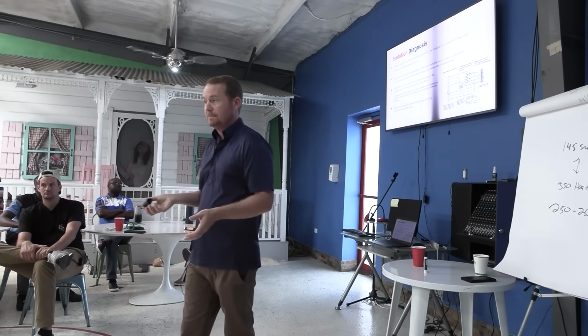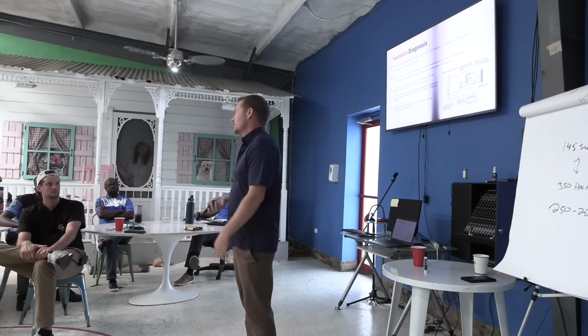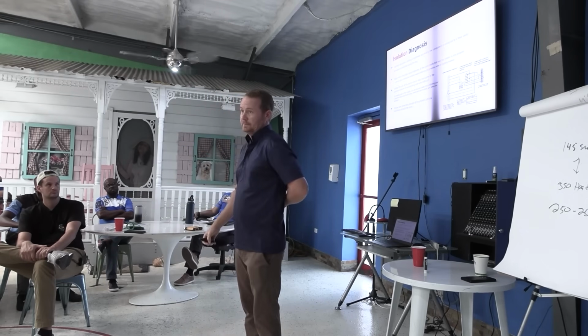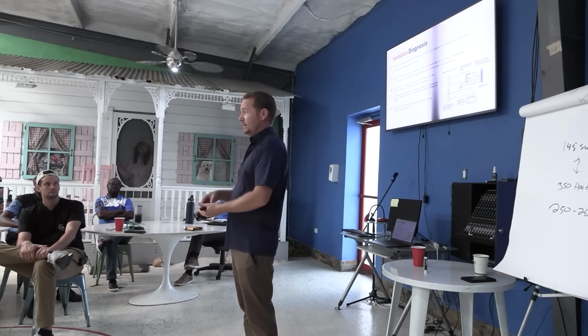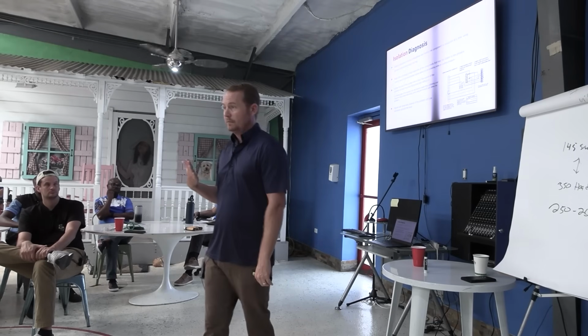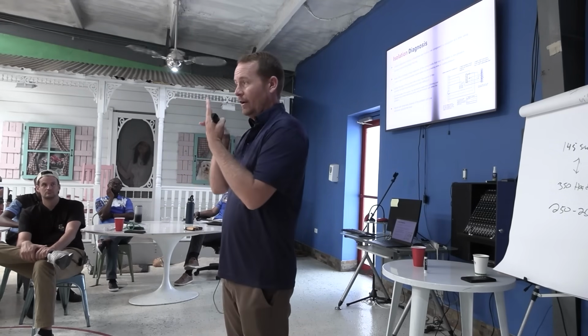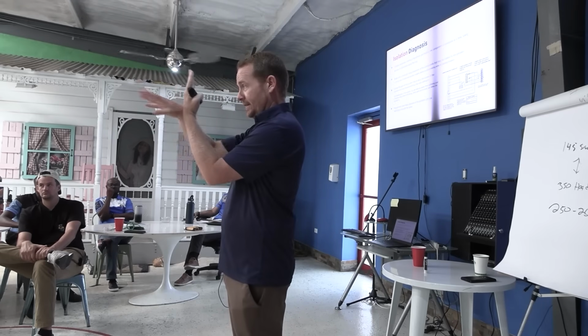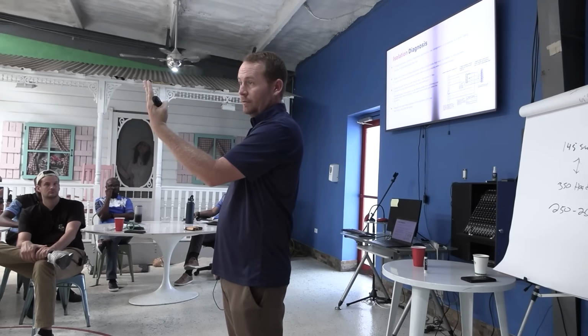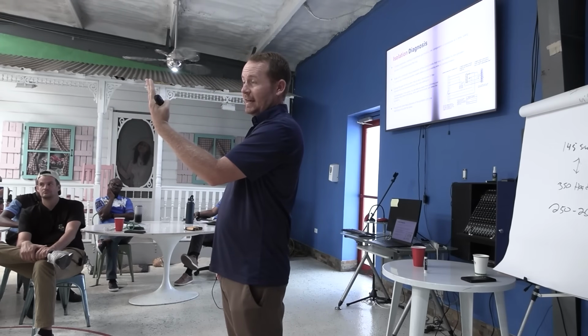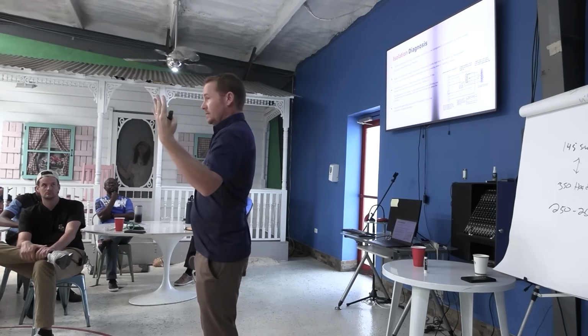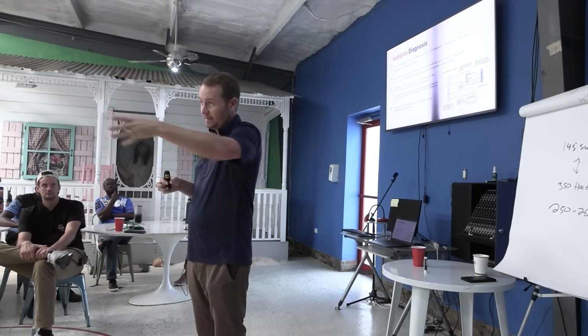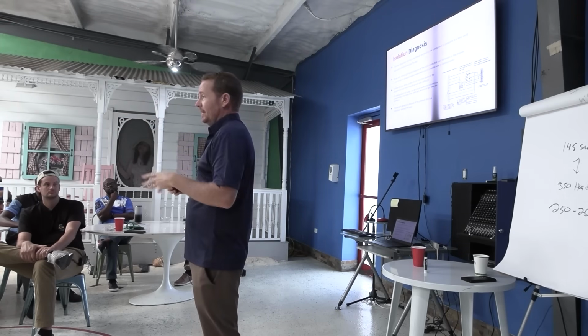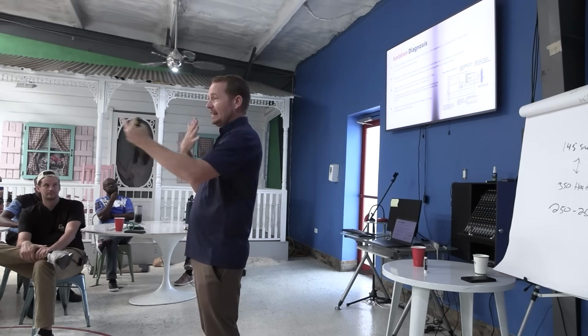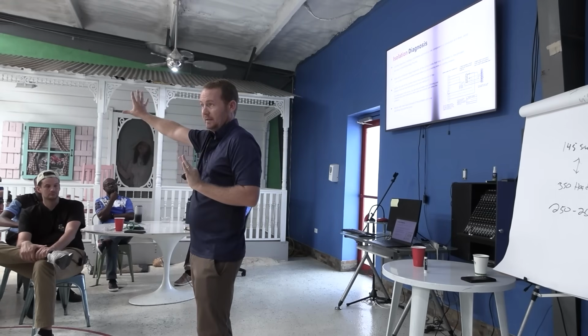But there are a lot of others. Say you think you have an evolution controller and the controller's bad. Take the controller off the wall, bring it to the air handler, and wire it up right to the air handler. You just want to see, does it work now? Because what does that eliminate, what does that isolate? That entire conductor. Now it doesn't isolate the conductor from the condenser to the air handler, which would be hard to do, but at least you're eliminating that possibility.